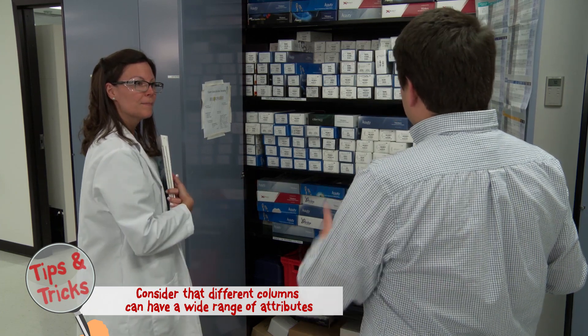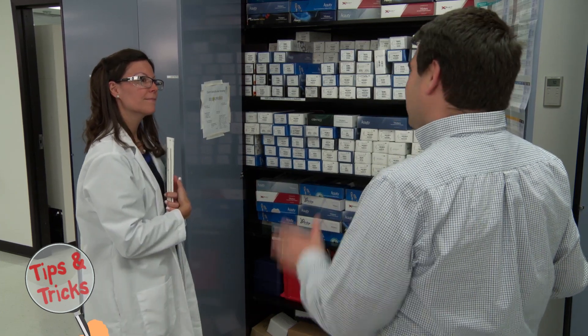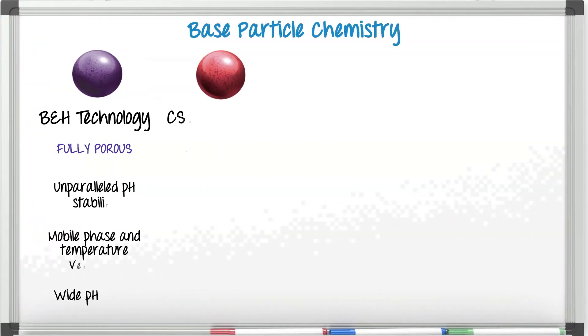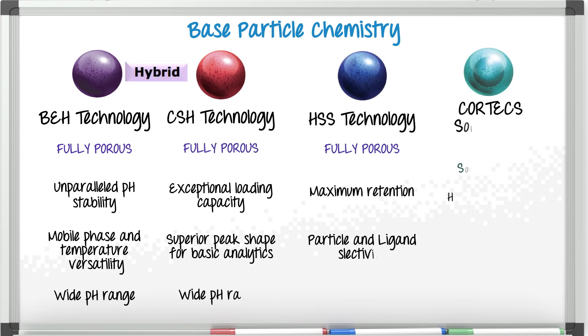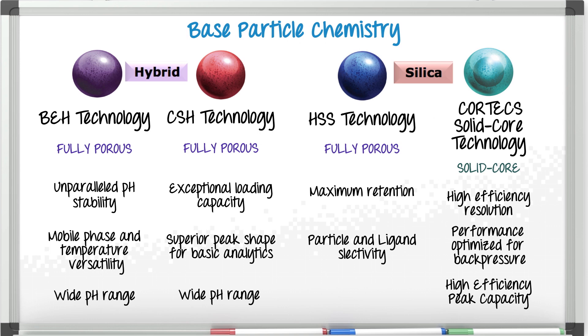There are quite a few, but I can show you a simple approach on how to select the right column for your separation. If we take a look at our base particles, to the left we have our hybrid particles and to the right we have our silica-based particles. Our hybrid particles — BEH technology and CSH technology — are excellent when used in alkaline mobile phase. Our silica-based particles, HSS and Cortecs, are designed for low pH mobile phase, with HSS having maximum retention and Cortecs having high efficiency and resolution.